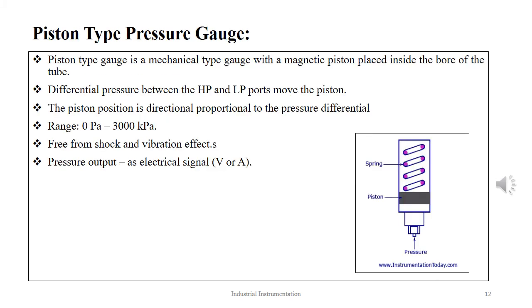The fourth type of elastic transducer is the piston type pressure gauge. This gauge has a magnetic piston and range spring in the bore of the gauge body. Differential pressure between the high and the low ports moves the piston in the bore against the range spring. The range of pressure measurement is 0 pascal to 3000 kilopascal. The position of the piston is directly proportional to the differential pressure.